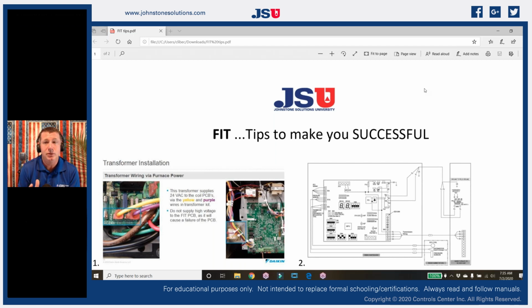Because remember, all that we did when we went to an inverter compressor is we took out the permanent split capacitor motor and we put in a true ECM motor. Same housing, we just swapped motors. So we're just getting a more efficient motor out of it, but we can have either an ECM constant torque with pre-programmed profiles or an ECM variable speed. So it depends on the actual manufacturer of equipment. All of our Daikin inverters are going to be those true ECM variable speeds. So they're going to use inputs to dictate what we're doing outside.